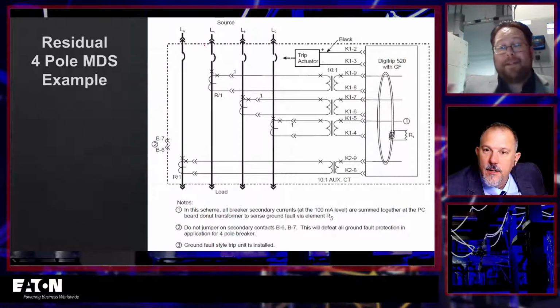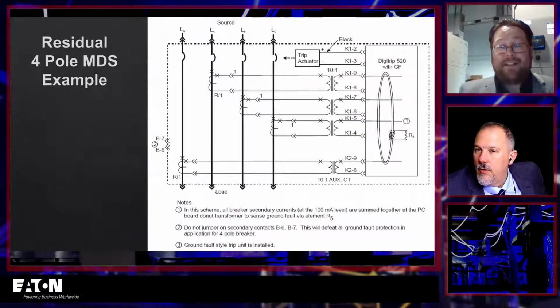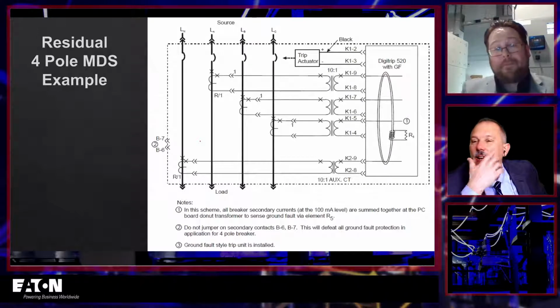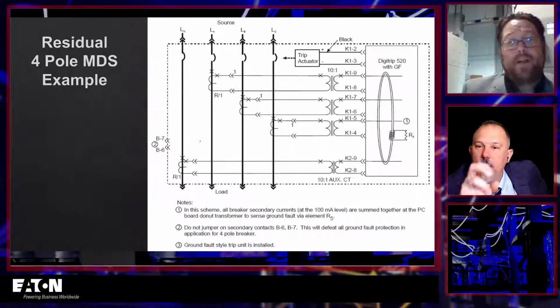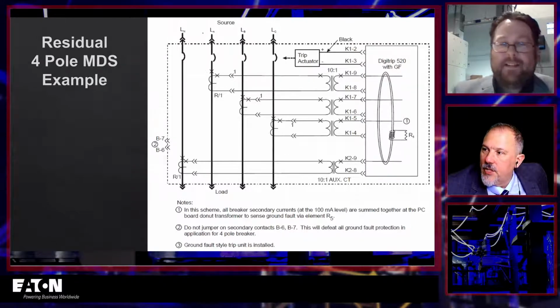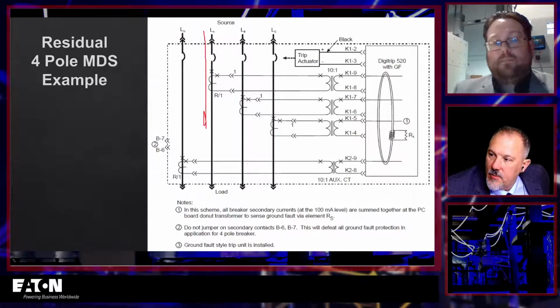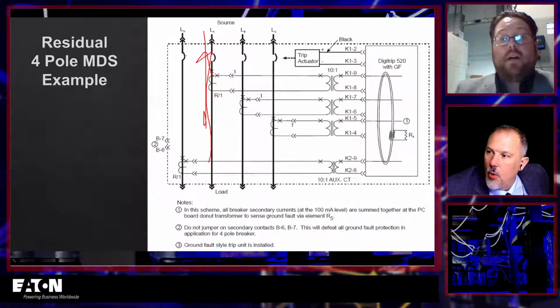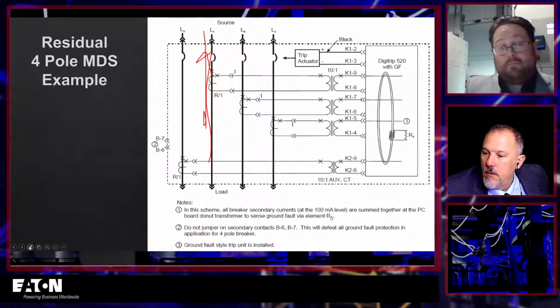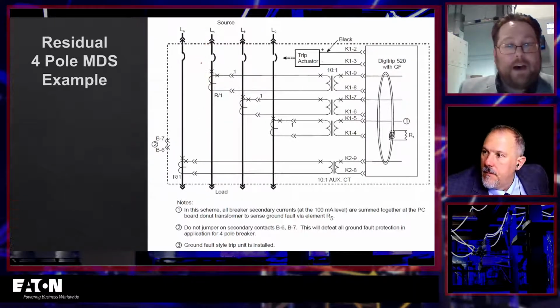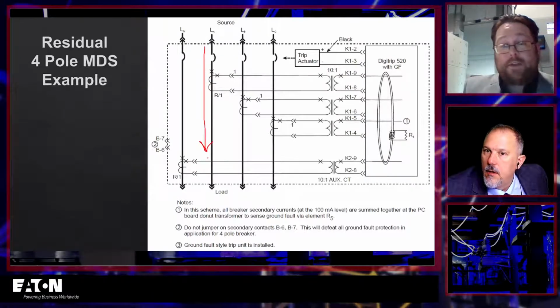So that's why you need to run the current back through it the opposite direction and make sure that it doesn't trip. If you run it through the same direction, it should still trip. So we've got to confirm the polarity. When you say run it through, in the first test you're coming this way. Are you talking about phase A pushing current back through that way? No. I'm saying phase A down, like through. So we want to do just phase A current going through. That should be a trip.